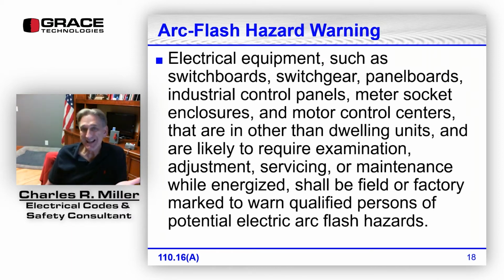So what's required to be marked? Well, is it liable to require adjustment, servicing, or maintenance while energized? And panel boards, yes. A transformer, I could argue both ways. I'm not going to put a label on a transformer because if I need to do anything with it energized, it's going to be closed up. I can do voltage testing on the downstream device, on the lugs of the equipment it lands into, the disconnect that it lands into.